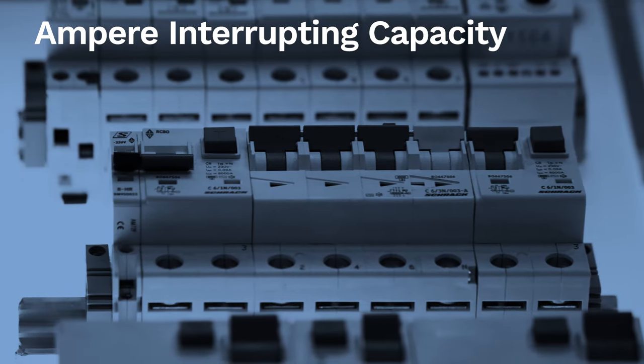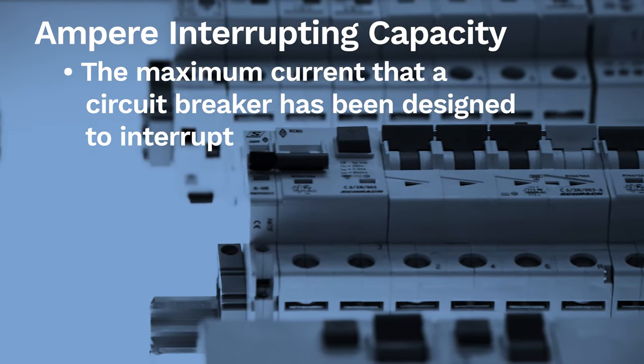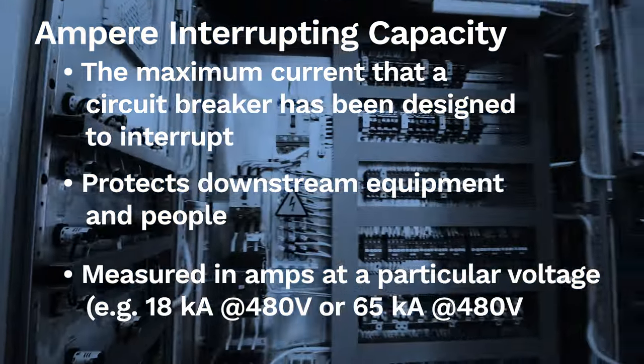Ampere interrupting capacity is the maximum current that a circuit breaker has been designed to interrupt, protecting downstream equipment and people. AIC is measured in amps at a particular voltage.